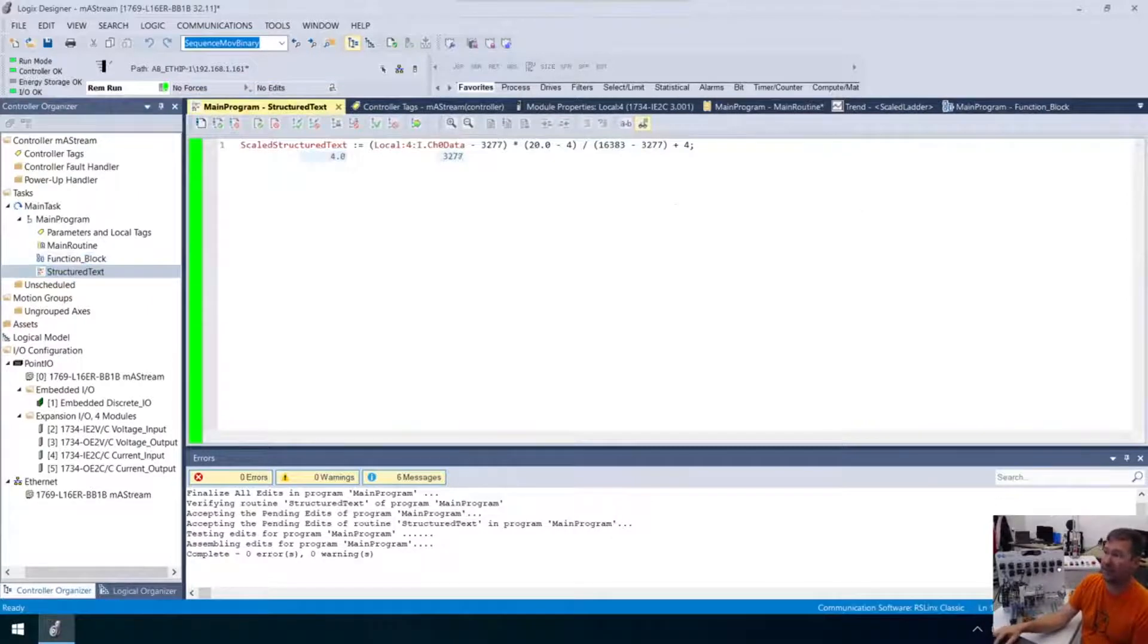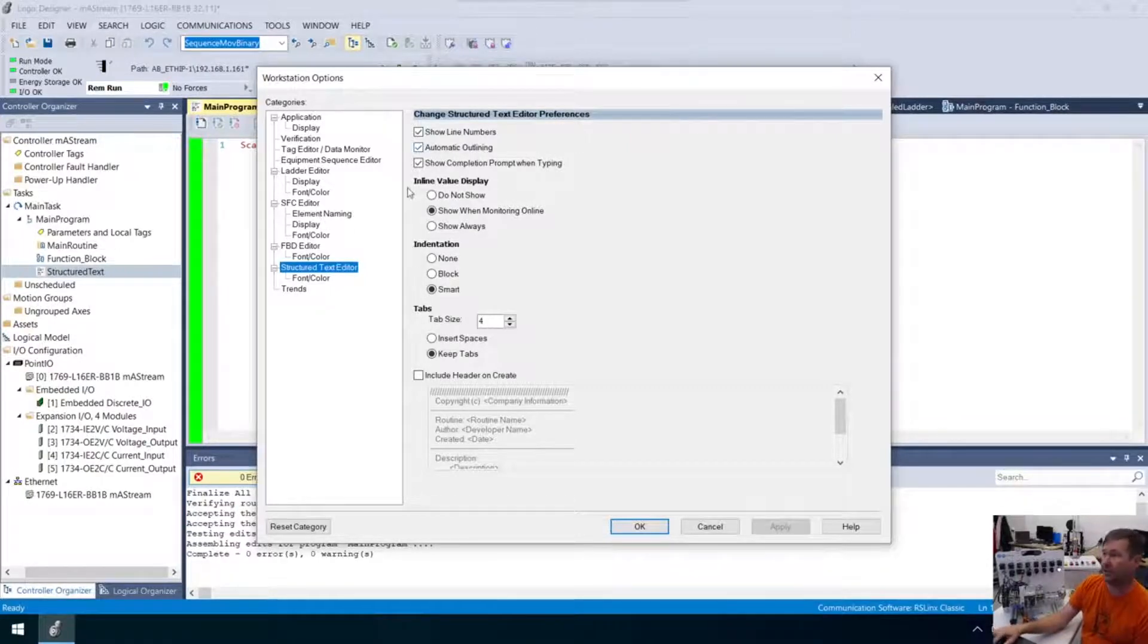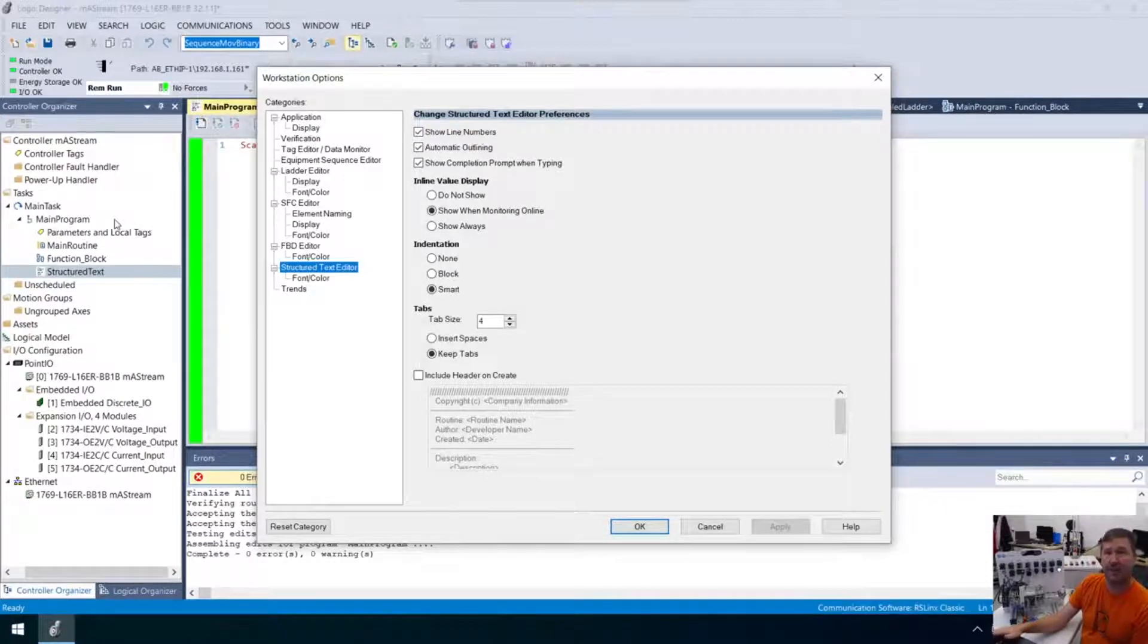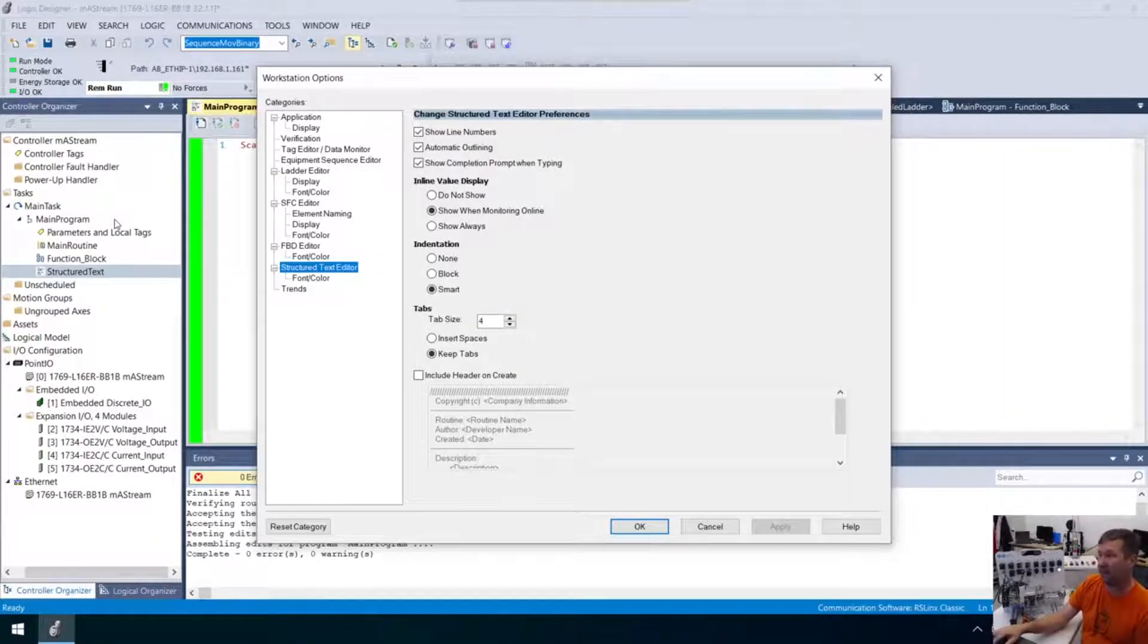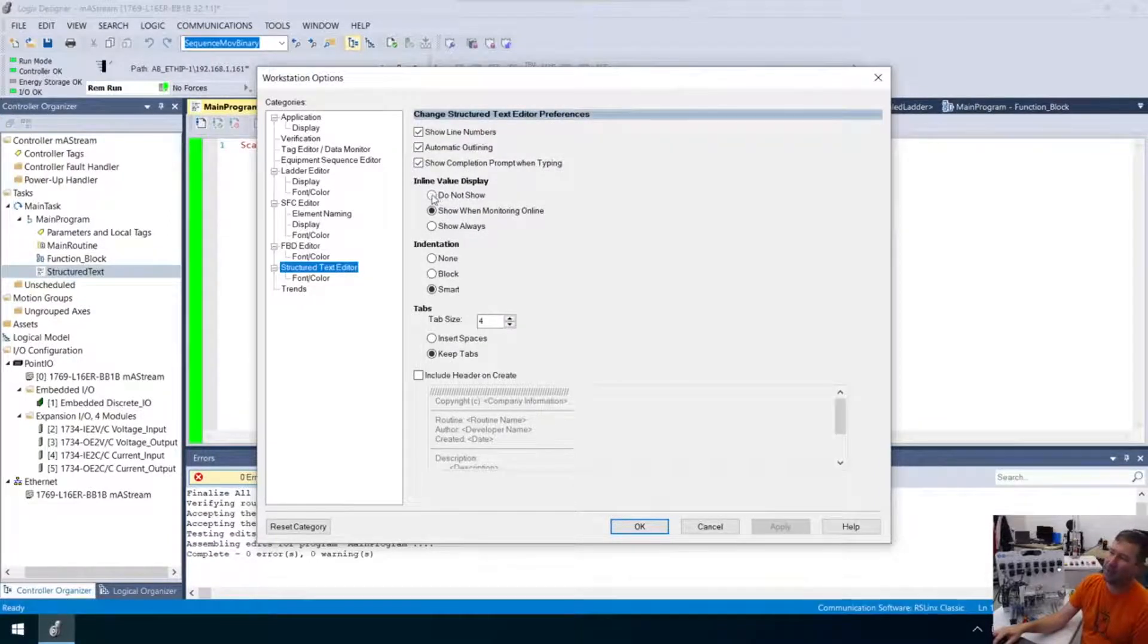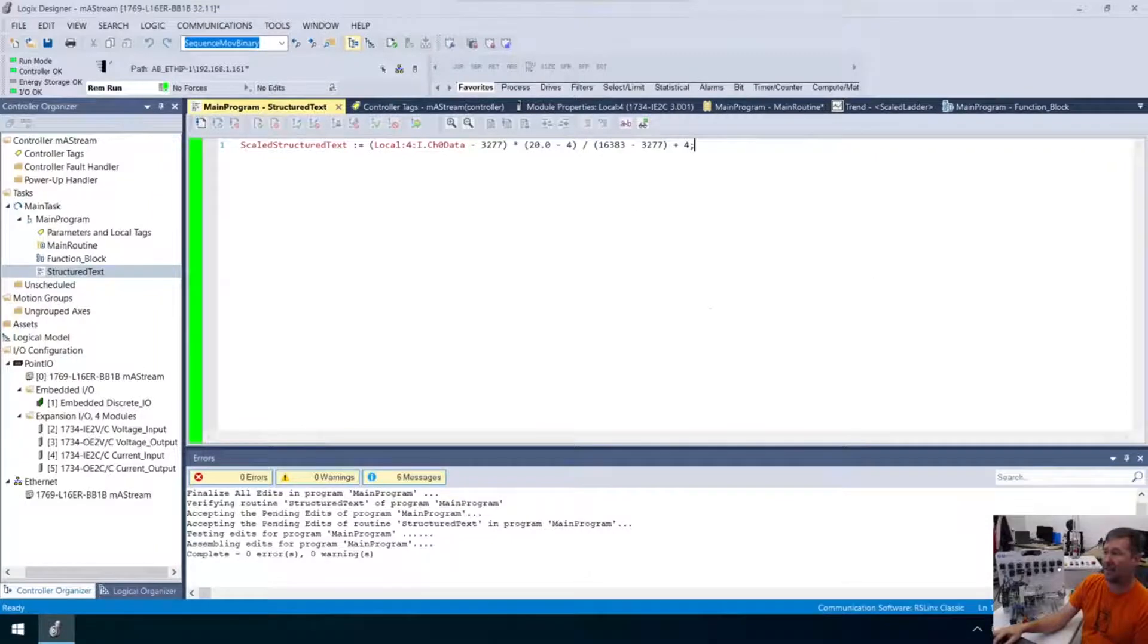And, honestly, this, I can't knock this. Now, I do need to knock one thing. Because, here's another thing that's not there by default. I'm going to right-click. Where is it? Am I right-clicking in the wrong place? Options. John, do I have a recommendation on where to learn structured text? We're actually getting ready to do a structured text lesson series. Some basics. They're going to be a lot like this. They're going to be Rosetta Stone type things. So, we're going to show how to do something in ladder, in function block, and in structured text. So, we can see how they function exactly the same. But, there is an issue here with structured text in Rockwell. Inline value display, by default, is do not show. So, by default, you're looking at this. And this is why people don't, this is what gives structured text a bad rap, I think, in Studio 5000.